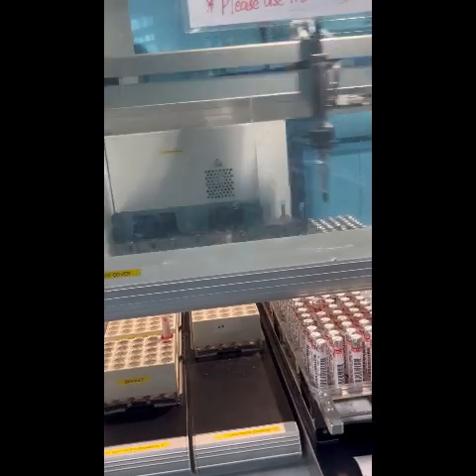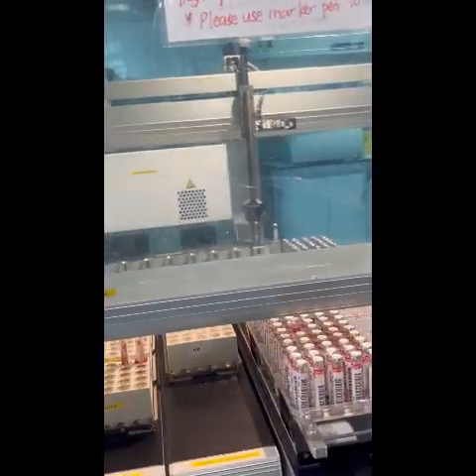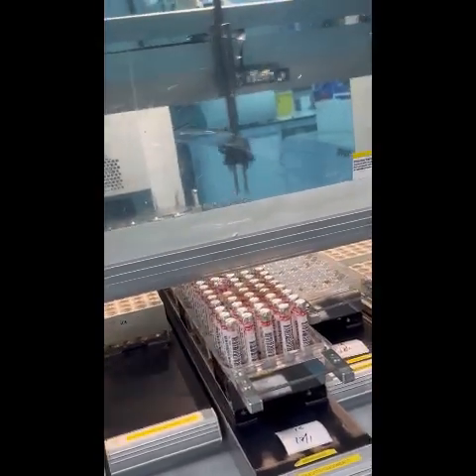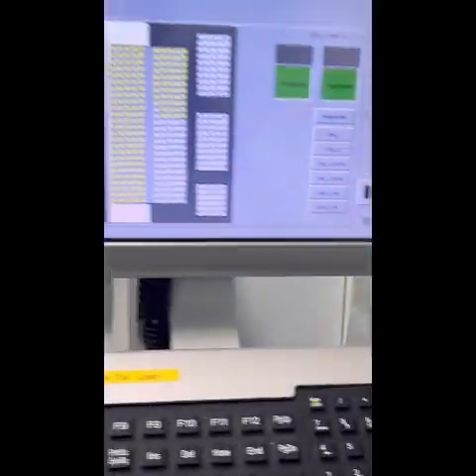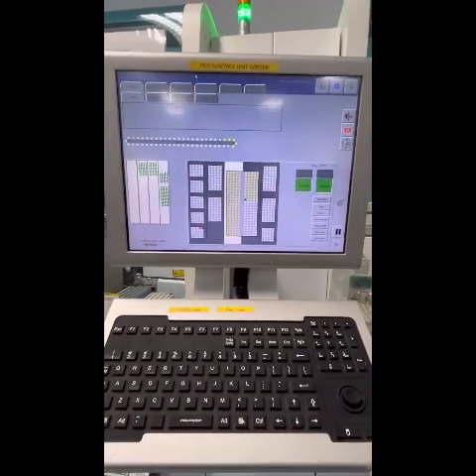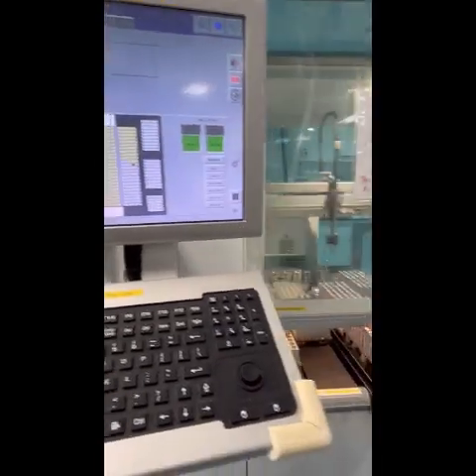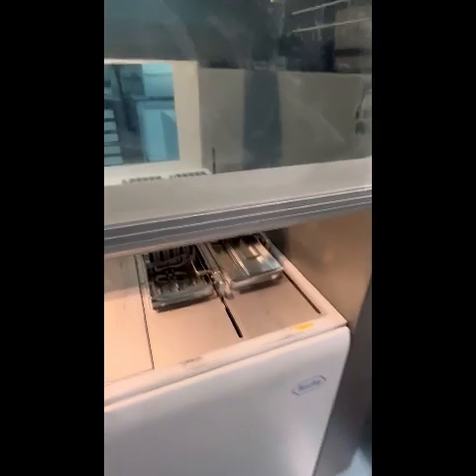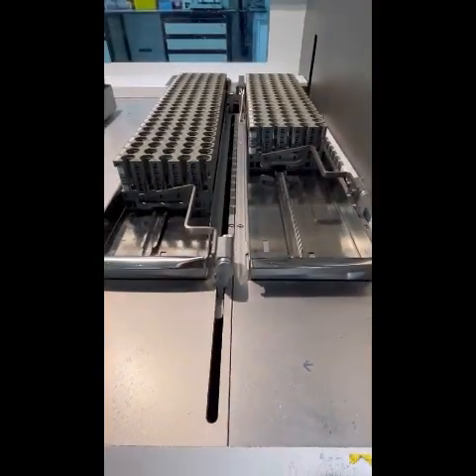Other than that, sometimes we will have a foil error, where there is insufficient foil, or the foil is placed in a different direction. Then it will give us an error, and we just have to change the type of foil. We also have this control unit screen to show us what's happening. As for these input trays, if there is a sample to run, it will come to this rack, and then this rack will be carried using the conveyor belt into the analyzer.